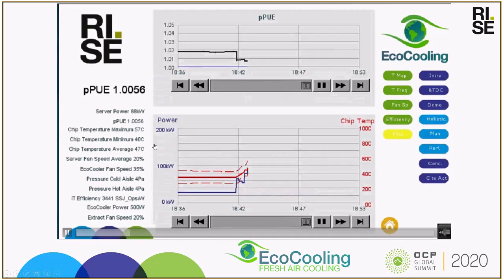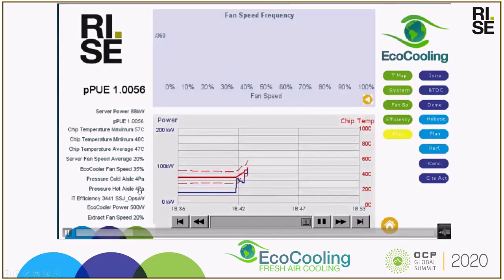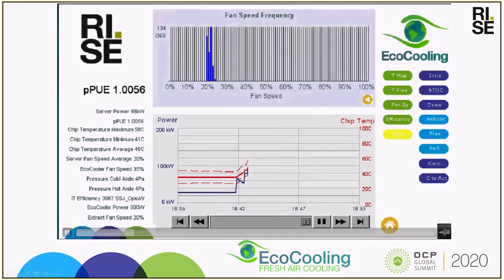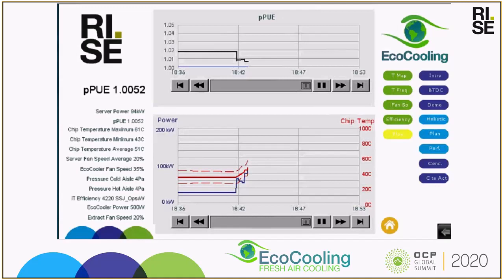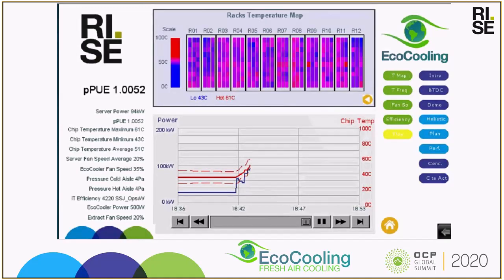So as you can see here, the pressure in the cold aisle relative to outside the room is 4 pascals, and the same for the hot aisle. So we've got no overpressurization of the hot aisle or the cold aisle relative to each other. The room is slightly pressurized, and you can see that we're measuring as the IT workload increases.